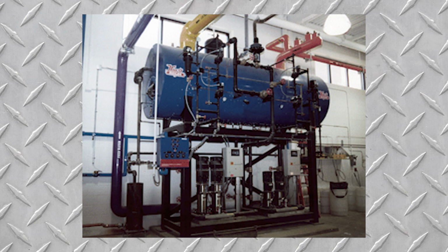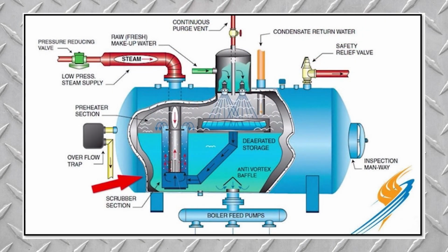The deaerator, meaning typically the condensate return tank, removes dissolved gases from the feed water. Now, using a valve at the top, we allow those gases to escape. But we'll also have to lose a little bit of steam. So there'll always be a small amount of steam escaping from the top. If it's a small amount, it's fine. But if it is a large amount, you might want to think about what's going on. Most likely you are returning actual steam through your condensate return tank from the steam system itself.